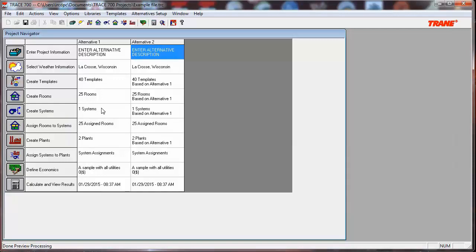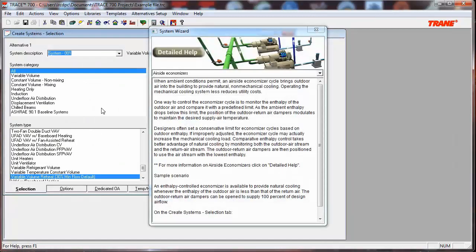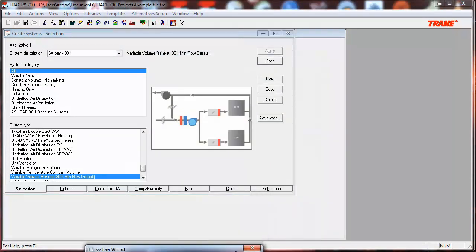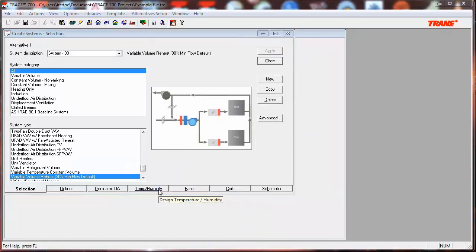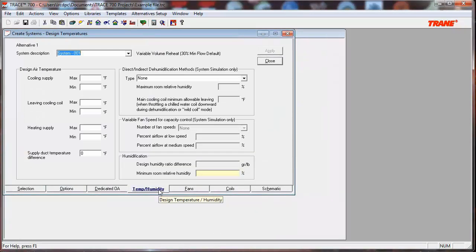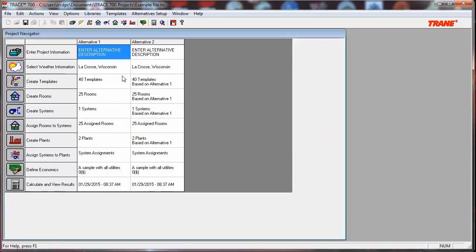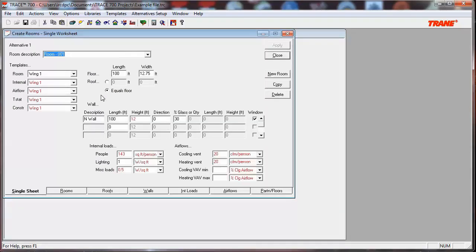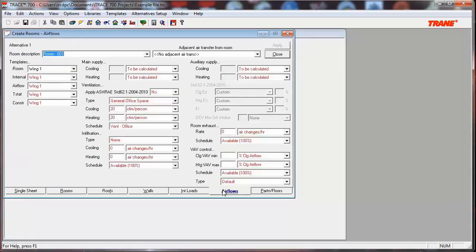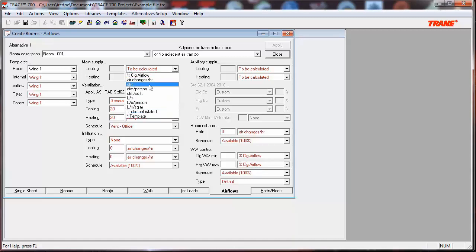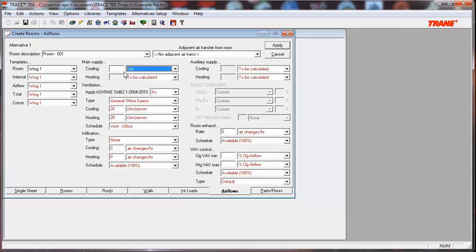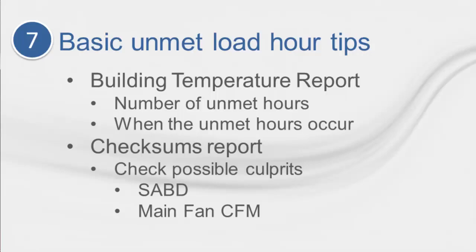If either of these situations occur, you have a few options to mitigate it. The first option is fixing the supply air dry bulb temperature. This can easily be taken care of by inputting a Design Supply value on the Create Systems section, Temp Humidity tab, Design section, Supply field. The second option is to adjust the CFM. The best method is to input an increased CFM rate in the rooms on the Create Room section, Air Flows tab, Main Supply section. This will force the Design Air Flow Rate to the specified value and provide more air flow to cover the load in the space. There can be many reasons for unmet load hours, but we hope that with a sound starting point and some basic places to look, it will increase your understanding of the software and your ability to troubleshoot your problems in a fast and efficient manner.